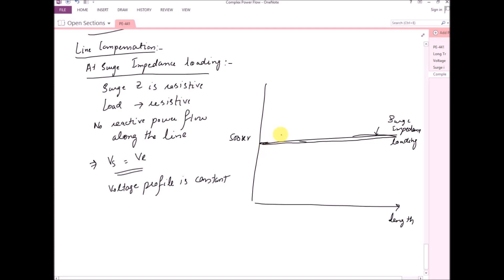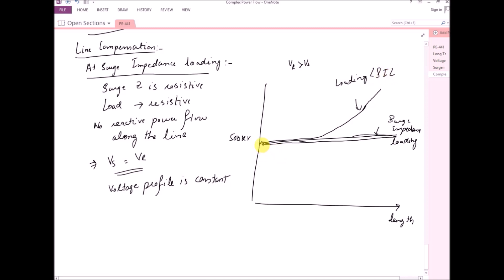If the loading is less than surge impedance loading, the voltage will be greater than the sending end voltage — as we explained in the Ferranti effect, when the receiving end current is zero or very small, we have Vr greater than Vs. And if loading is greater than surge impedance loading, the voltage will be decreasing towards the receiving end, so there is a voltage drop.